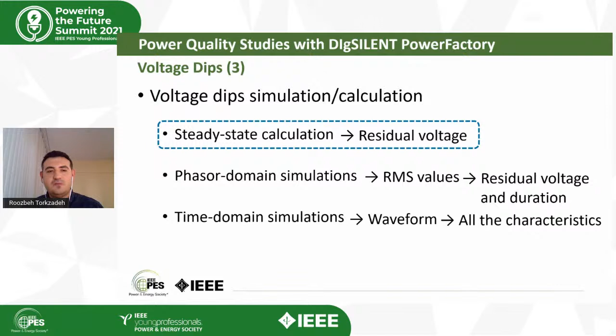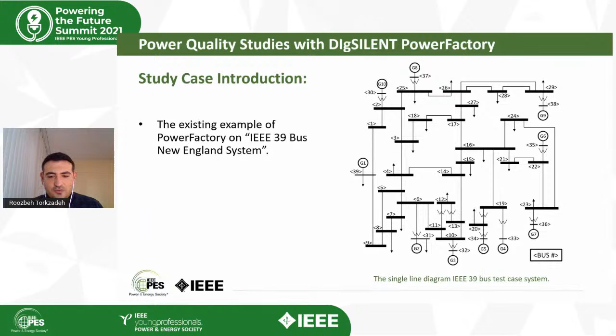According to the requirements of each study, we need to pick a proper method. In this workshop, I'll investigate the voltage dips in the presence and also absence of renewables. Therefore, a steady state calculation would be enough, especially because we are focusing on the grid level. So steady state would provide us enough information to reveal what will happen in future with renewables. Before switching to PowerFactory to show you how we do this calculation and simulation, it's better to introduce the model. I'm going to use the IEEE 39 bus test case system, which has a 345 kV transmission network. This model exists within the examples of PowerFactory, so you can easily use that model. And now let's switch to the software.